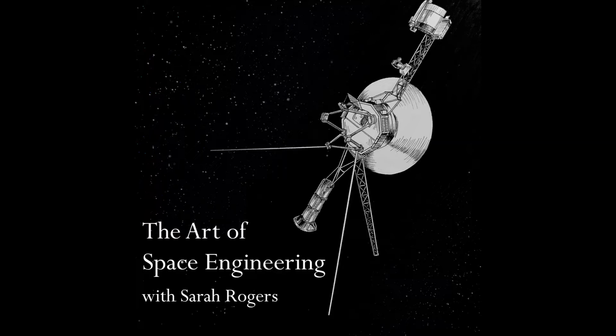So if you are building an instrument and you've got all kinds of stuff, either dirt or grease that's gotten into the instrument, or the electronics boards, once they heat up, start to outgas volatile material, particulates and volatiles can get in the way and absorb those ultraviolet photons before they ever get to the back end of your instrument, to the detector that's going to record the photons. And so you have to go through this process of building the instrument in an extremely clean environment. And that is very challenging in a lot of regards.